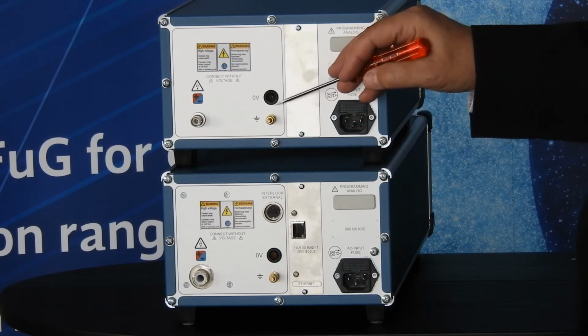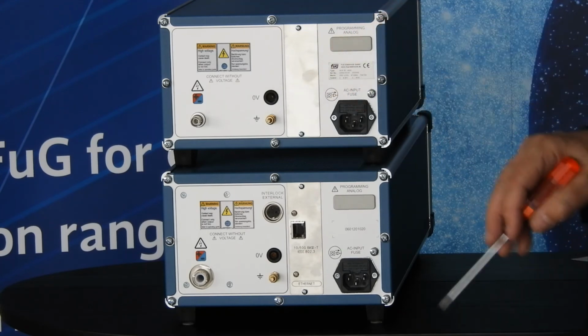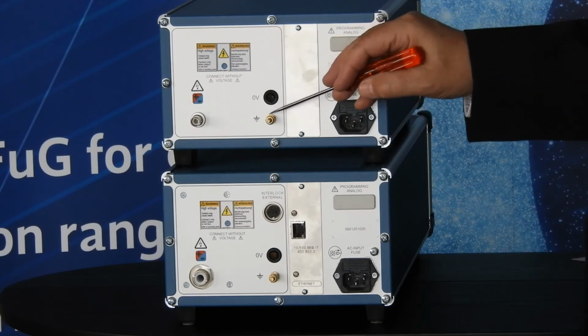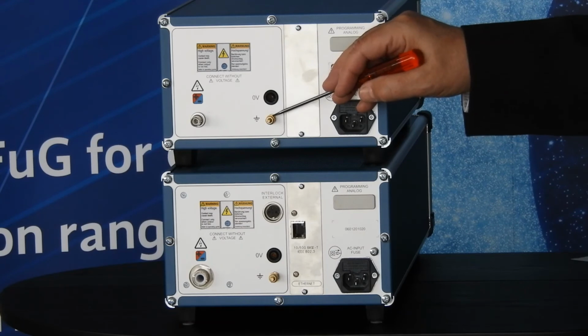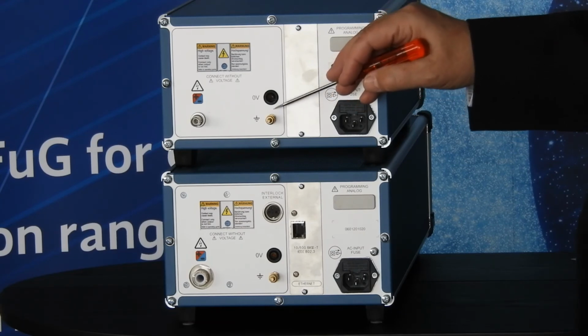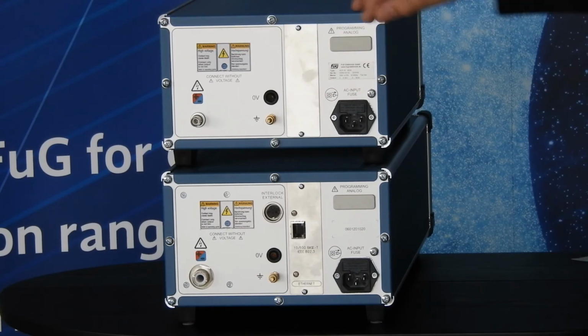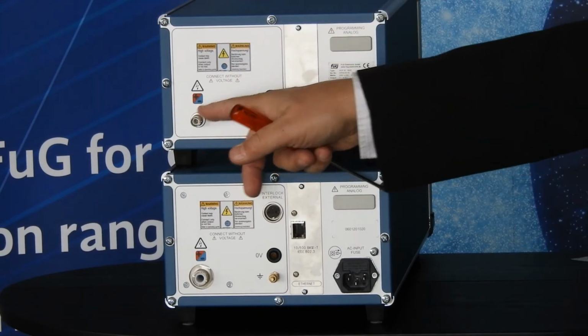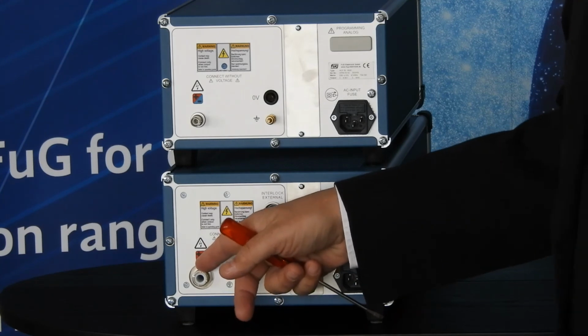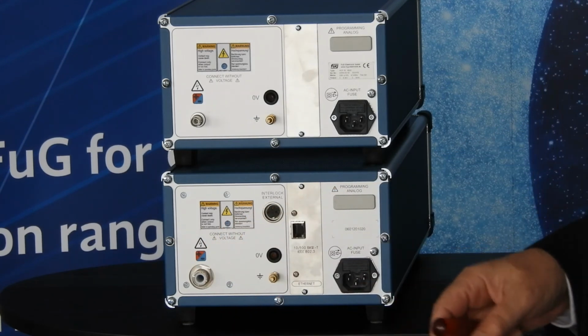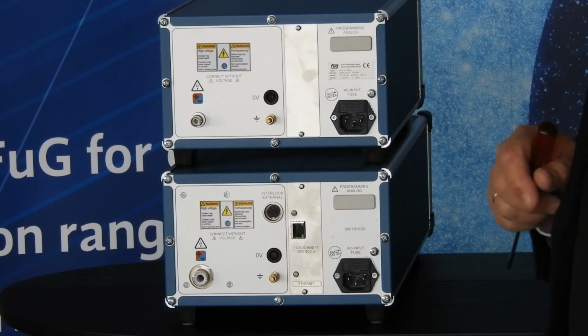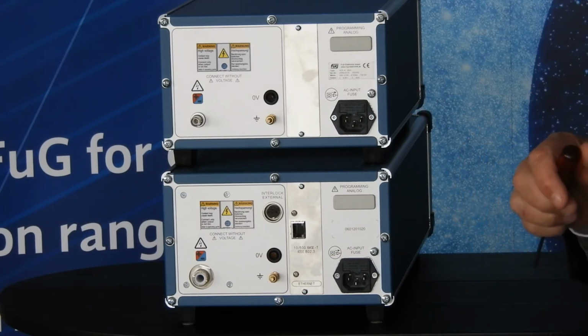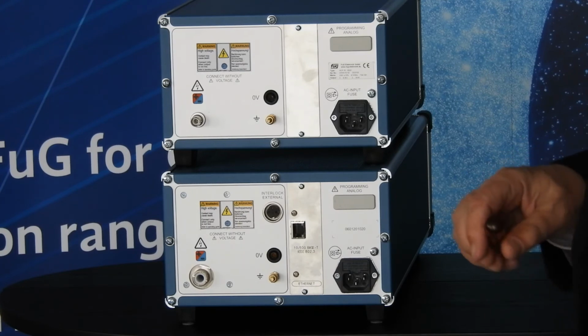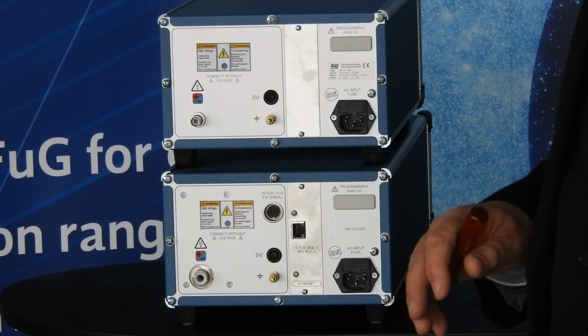Normally when we deliver the power supply, the bridge is installed and 0-volt is connected to the power ground, and so to the case of the power supply, to all touchable screws and so on, and also to the screen of the output connector if there is a high voltage output connector, and to the cable. So in this usual configuration, you can use the screen of your high voltage cable to let the current flow back to the power supply.